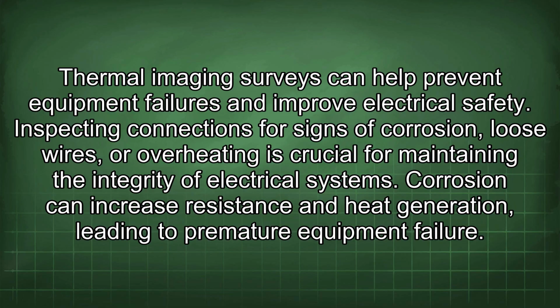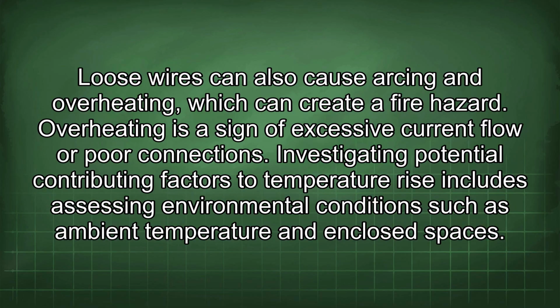Inspecting connections for signs of corrosion, loose wires, or overheating is crucial for maintaining the integrity of electrical systems. Corrosion can increase resistance and heat generation, leading to premature equipment failure. Loose wires can also cause arcing and overheating, which can create a fire hazard. Overheating is a sign of excessive current flow or poor connections.